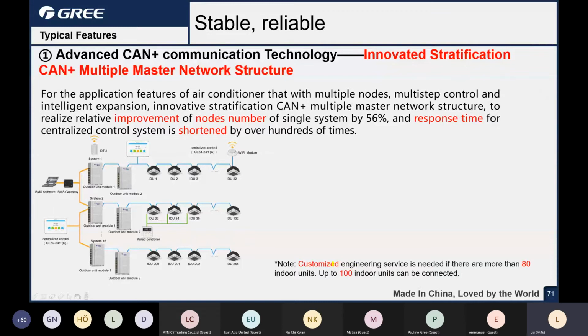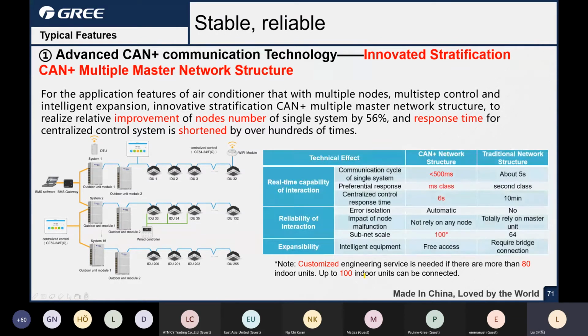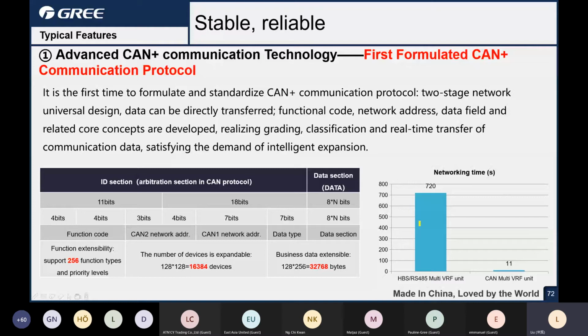But it must be customized. 100 indoor units maximum. It needs to be customized. Okay. And for the communication, the cycle for one system is less than 500 milliseconds, and the response level is milliseconds class. Okay, and the indoor units quantity is 100. And that's the advantage of CAN Plus. So it's faster, and bigger indoor units installation amount than the previous generation and the other brand. This is also CAN Plus.